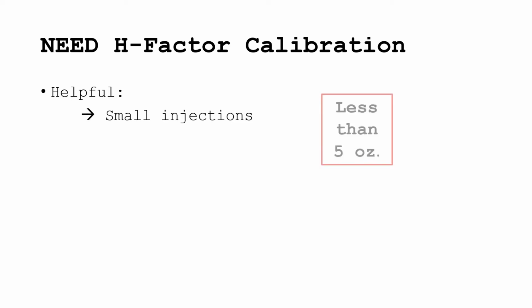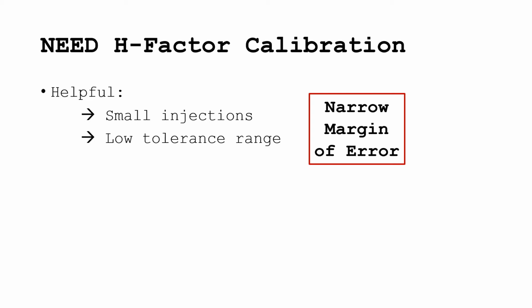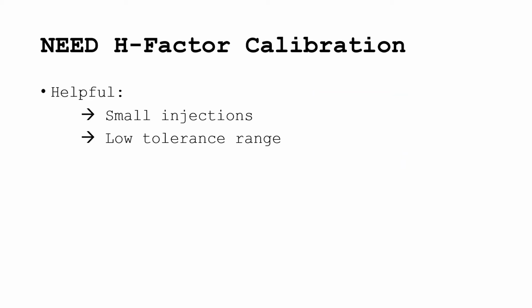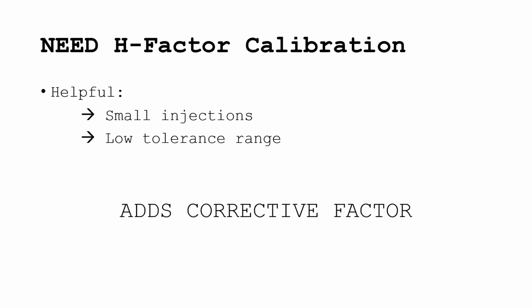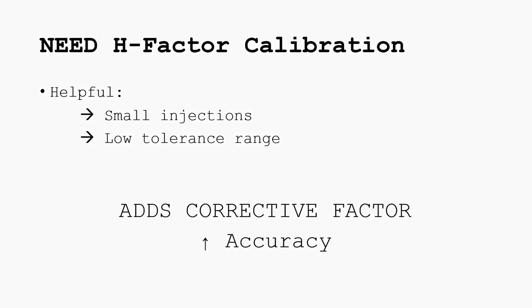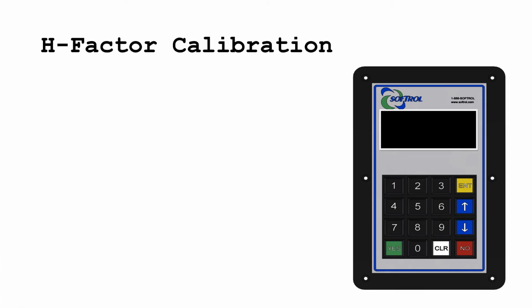Not all chemical injections need an H-factor calibration, but it is helpful in certain situations, like when the injection size is small, less than 5 ounces, or there is a low tolerance range or a narrow margin of error. The H-factor calibration does not change the calibration but adds a small corrective factor to the injection in order to increase its accuracy. You do an H-factor calibration using a very similar method to all other types of calibrations.